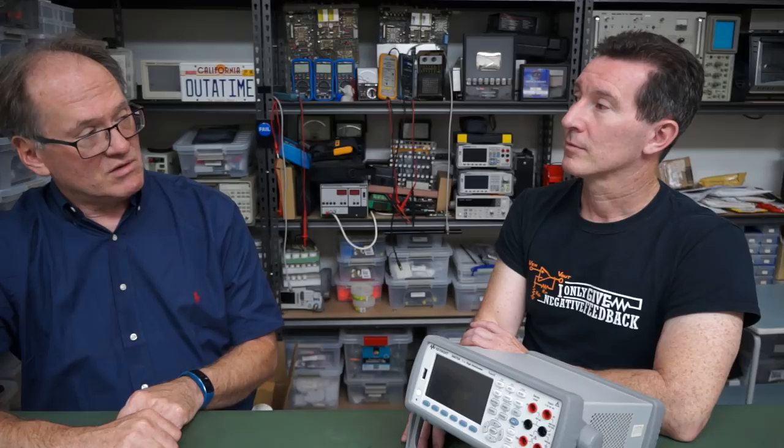When it gets to the design team, depending on how hard it is to fix the bug, that can take a couple days. It can take a couple weeks. If it's a case of a memory overflow that only happens on a rare occasion, that's the hardest thing to catch. That might take two, three, four weeks to get it, catch it with its pants down, so to speak. Once you find it, it takes very little time to fix it. And then it takes typically a week or two to guarantee that we didn't break something else. We do exhaustive testing before we ship a firmware update out. Because the worst thing you can do is fix it and break something else.